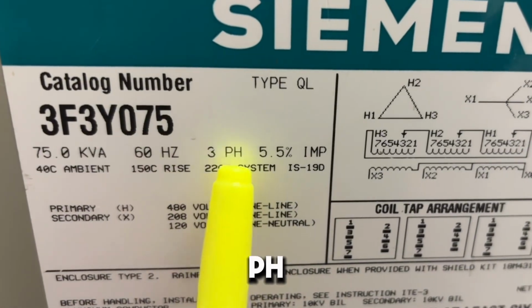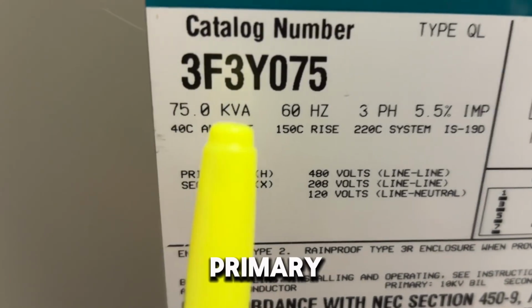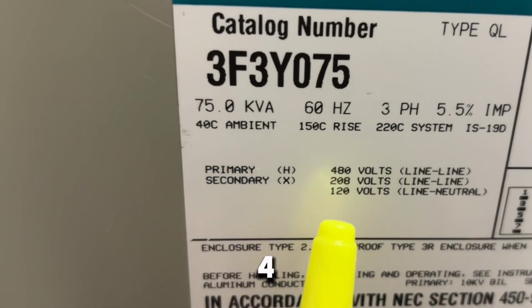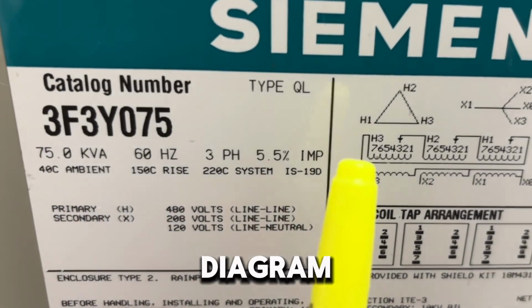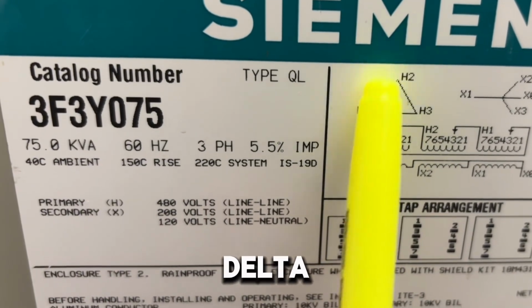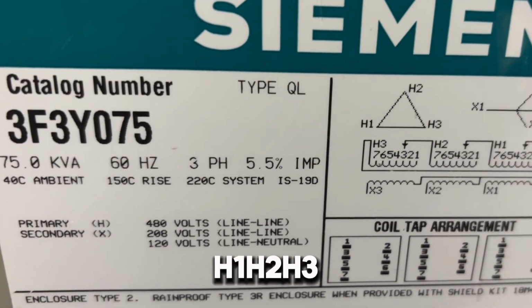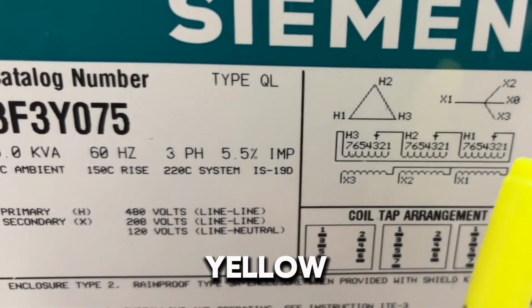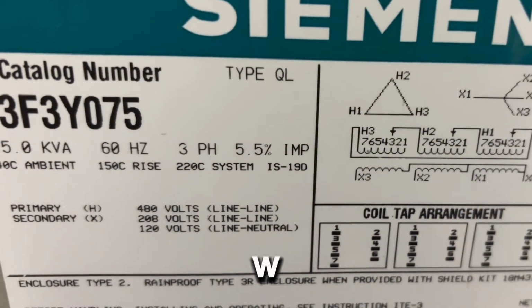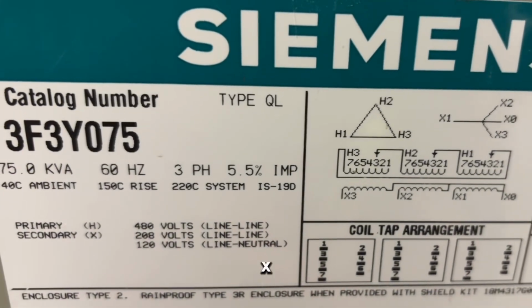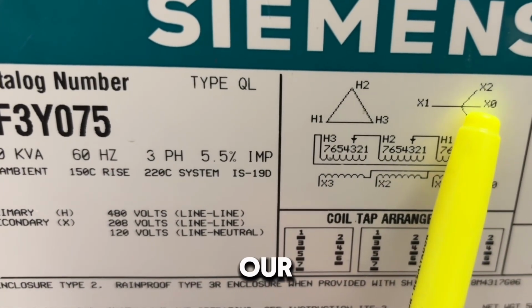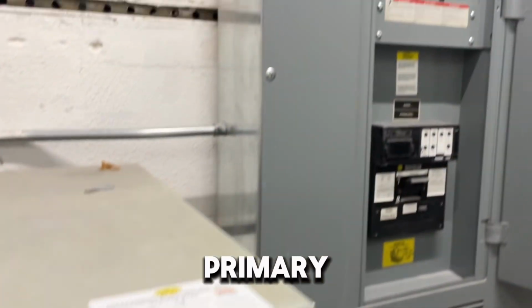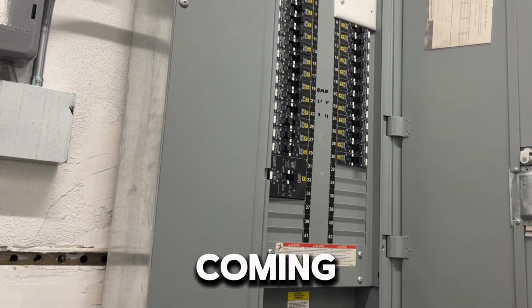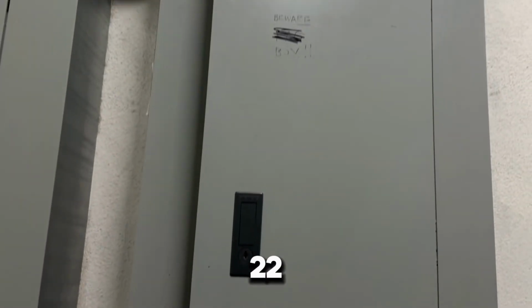We have 3 PH for 3 phase, and then our primary, and then our secondary, primary 480, and then secondary 208. Now our actual wiring diagram, we have the primary coming in as a delta being a triangle, H1, H2, H3, which is your brown, orange, yellow. Our secondary being a Y, a wye, X1, X2, X3, and our X0, that is our neutral. So we have our primary 480 is delta coming in to our secondary, which is our Y 120/208.